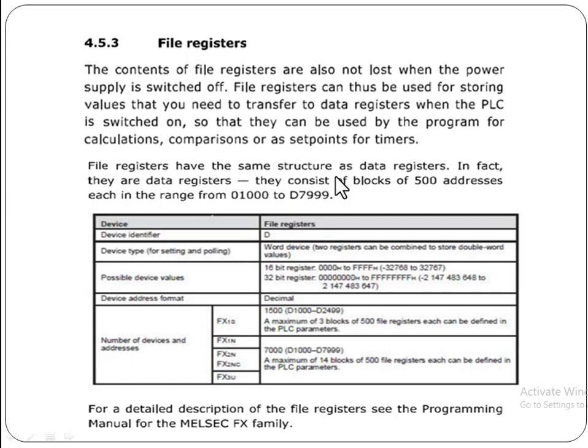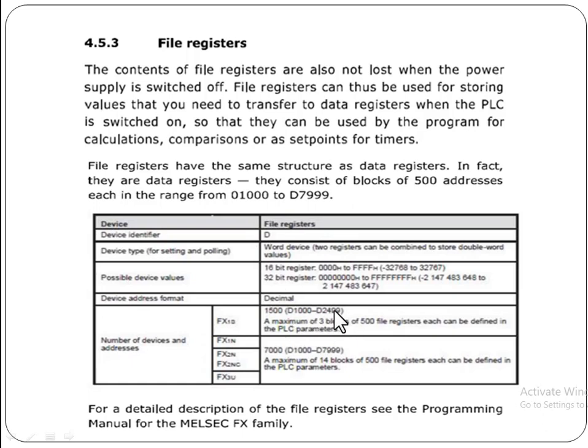File registers have the same structure as data registers. In fact, they are the data registers. They consist of blocks of 500 addresses each, in the range from D1000 to D7999. They are also denoted with D, and are available in 16-bit and 32-bit register formats. Device addresses are in decimal format, and they are present in the form of blocks of 500 file registers.